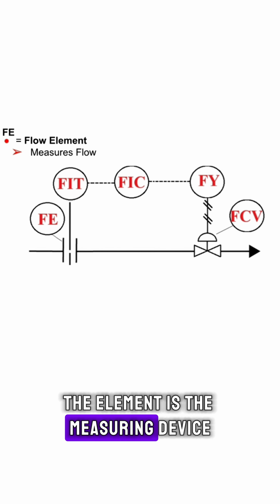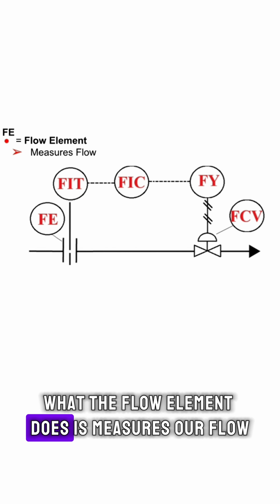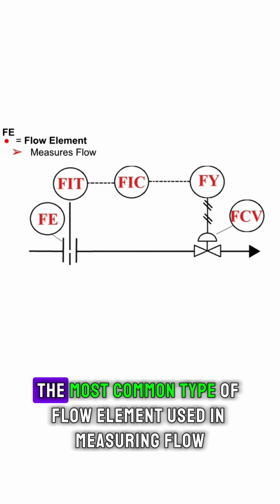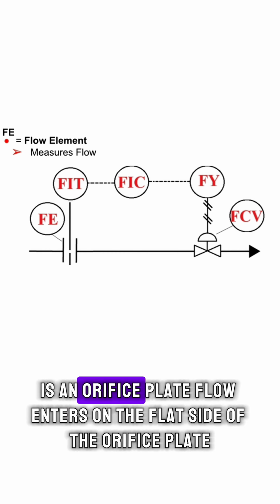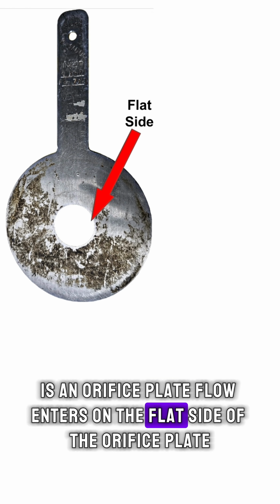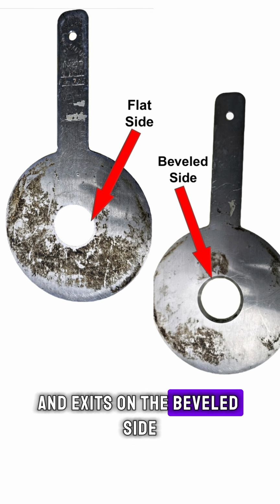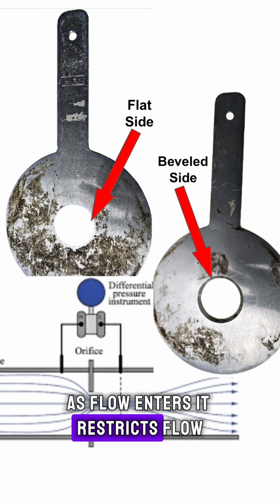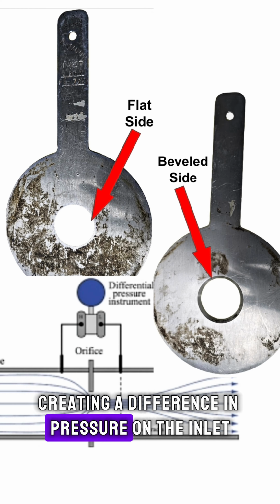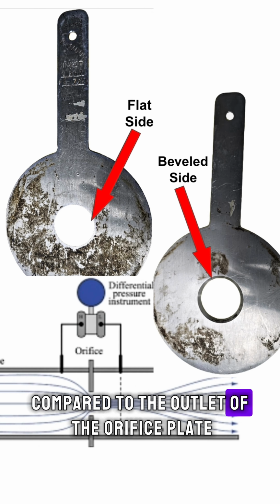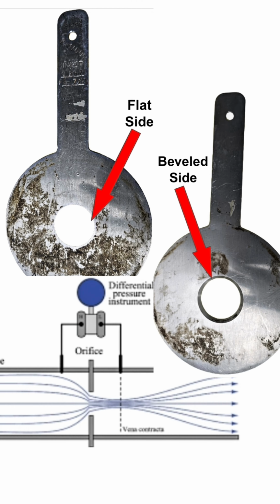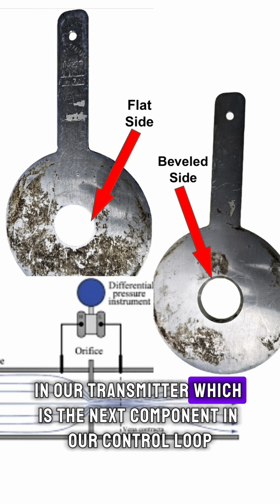The element is the measuring device. What the flow element does is measure our flow. The most common type of flow element used in measuring flow is an orifice plate. Flow enters on the flat side of the orifice plate and exits on the beveled side. As flow enters, it restricts flow, creating a difference in pressure on the inlet compared to the outlet of the orifice plate. This difference in pressure is converted to measure flow in our transmitter, which is the next component in our control loop.